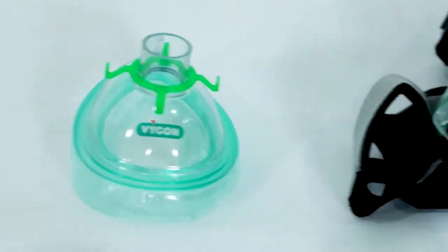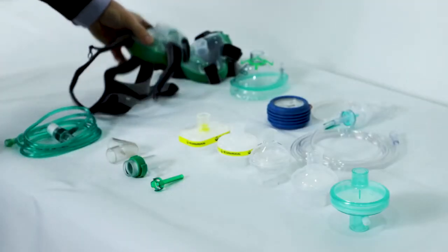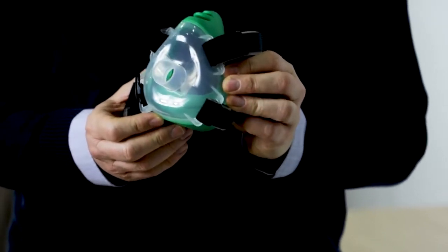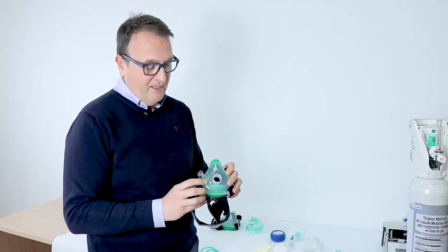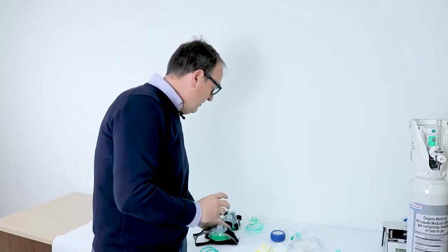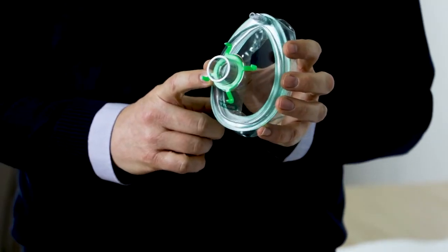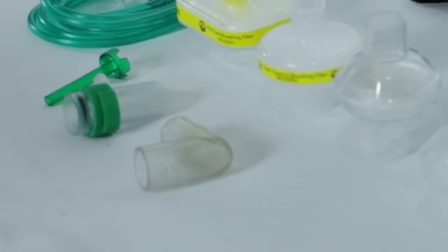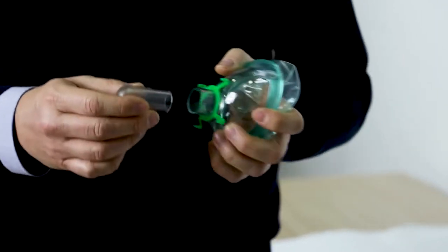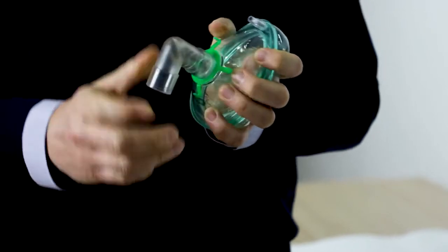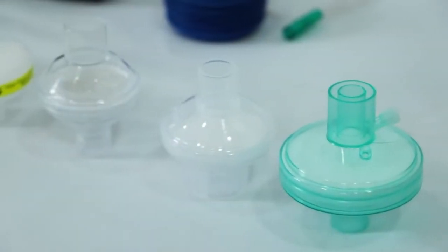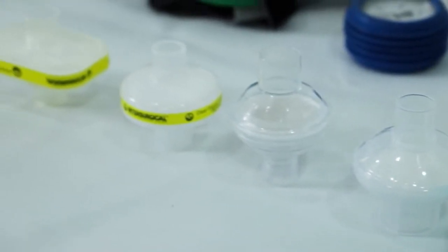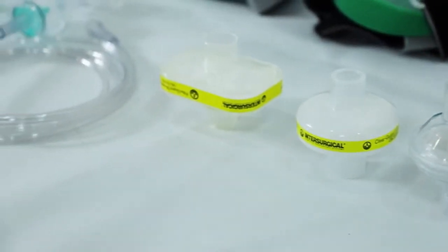First of all, I'm going to show you how to assemble the filters in the Boussignac CPAP systems. The first step is to choose the face mask. We can choose whichever. This face mask is a very comfortable face mask for the Boussignac valve, or we can use this one that is available in some European countries. The first step is to fit the elbow. We are going to put here the elbow. It's an ergonomic elbow. Secondly, we have to choose between the different filters. As you can see, all the filters fit perfectly.